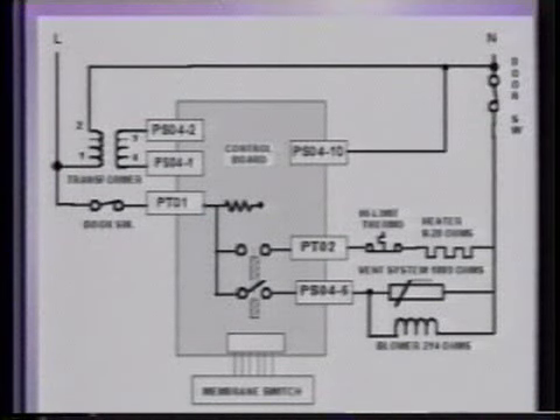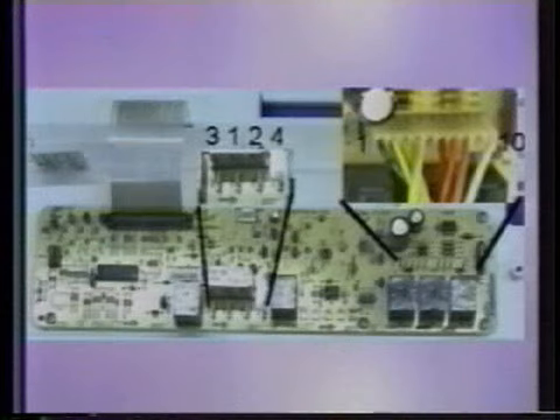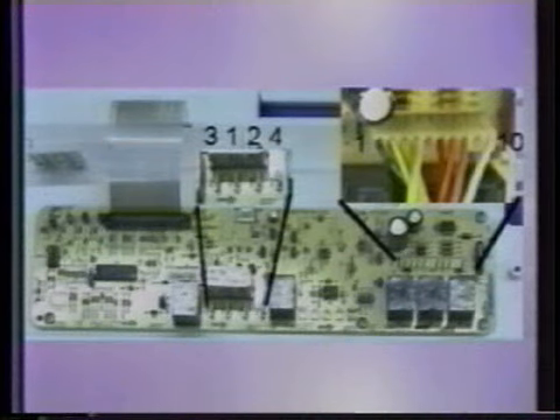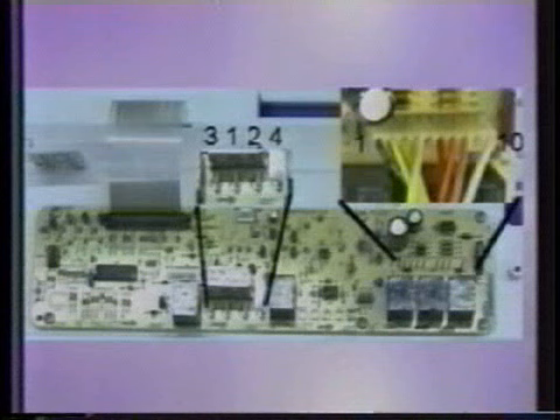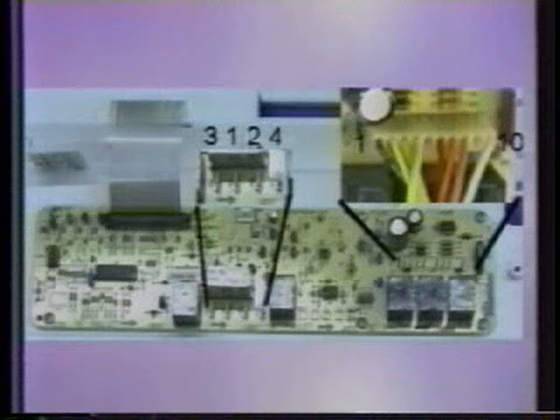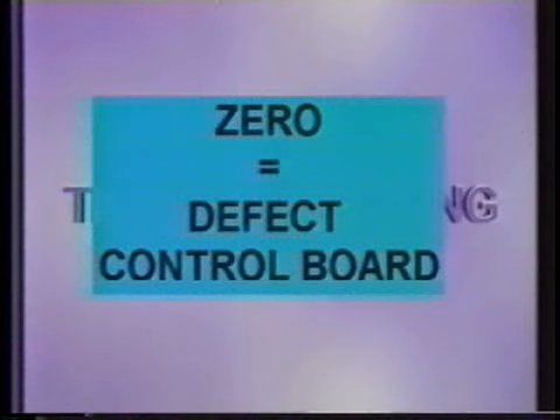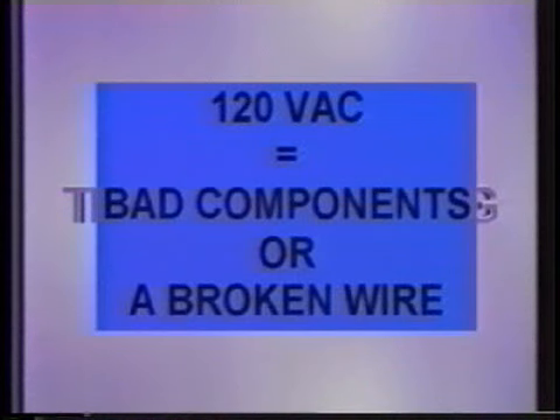Let's see how we would check that. If both of them do not work, what we would do is go back to our board and go to pin 6 of the 10-pin plug and measure between there and neutral to see if we have 120 volts out. If we have 0 here, we've got a bad board. If we have 120 volts, then we're going to have to go out to one of the components and measure voltage here.